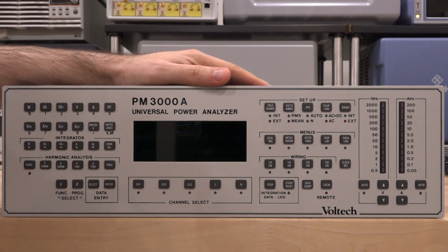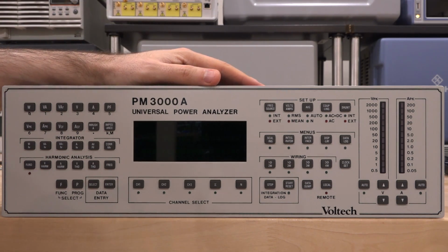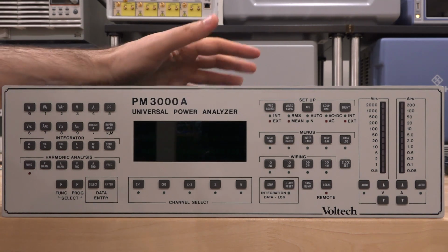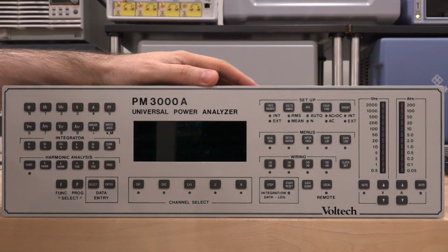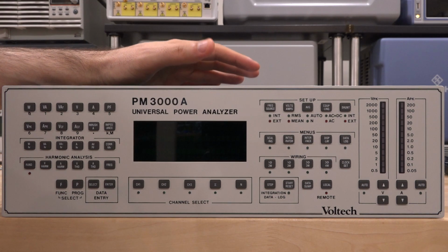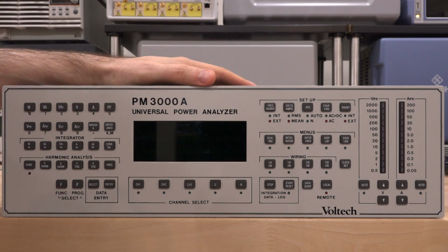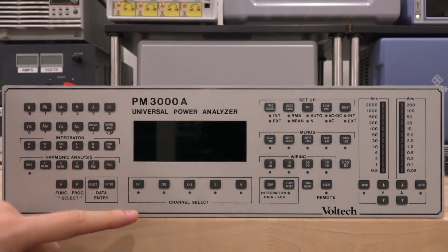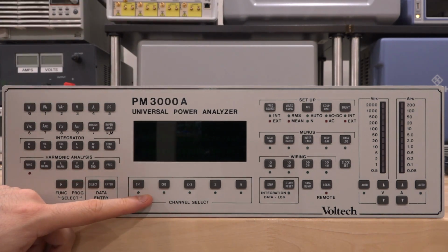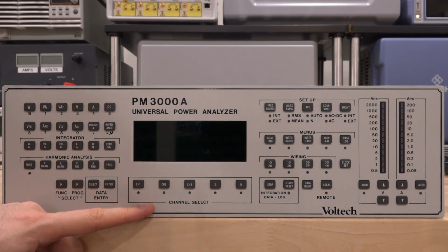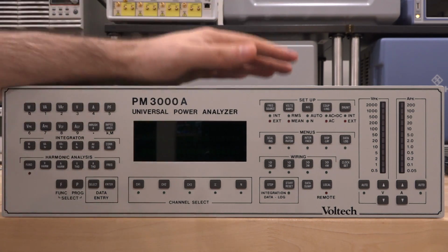I've actually done power analyzer repairs in the past. I did a Fluke handheld one quite a while ago, but I've never done a 3-phase one. So we can take a look and see what it looks like on the inside and see the fault here in just a second. Now, fundamentally, a power analyzer is really nothing more than a 6-channel digitizer, because you have 3 channels here. You need to digitize voltage and current. So really, if you have a 6-channel oscilloscope, essentially, you can do all the algorithms on the waveforms coming from that.